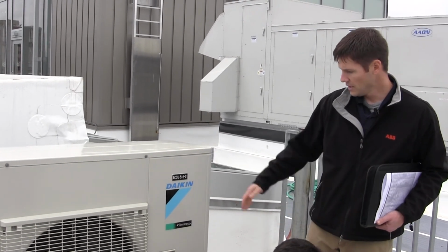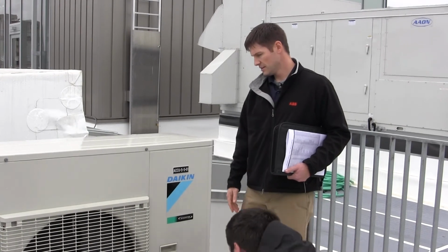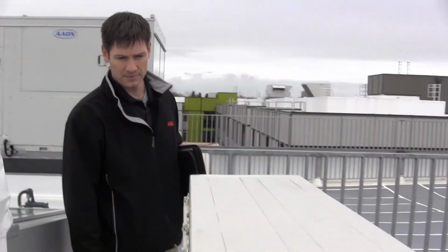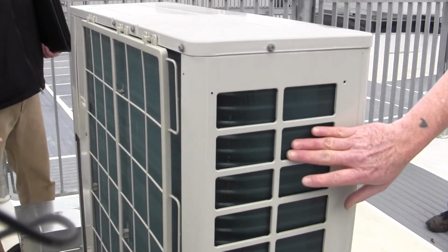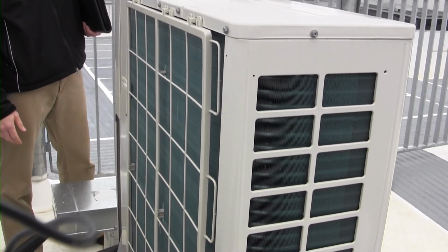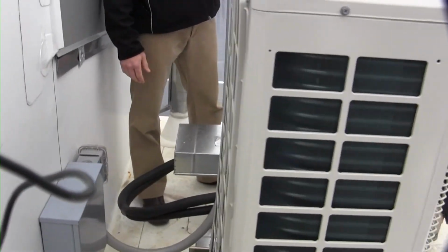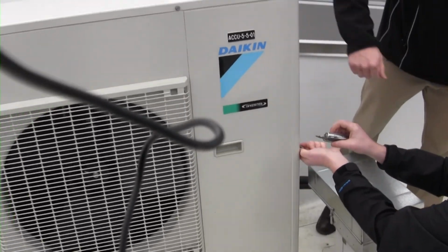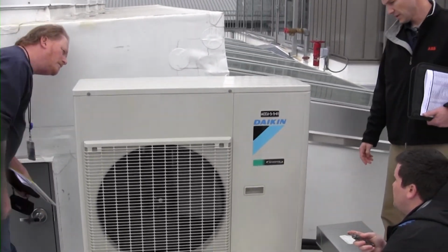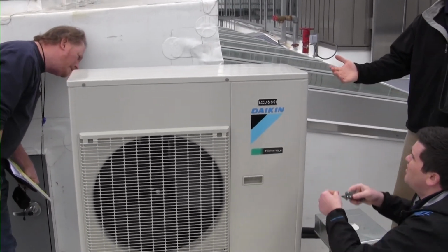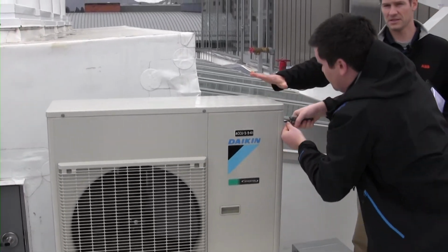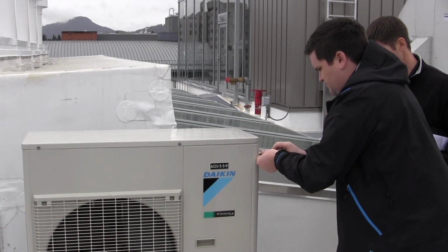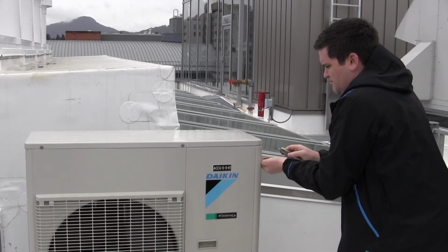On the inlet side over here, you can see the coil is slightly blue. That's an acrylic anti-corrosive coating. Very thin layer, doesn't change any heat transfer properties. The air gets drawn through and comes out the fan on this side. And since this unit will always be cooling indoors, that means this is basically heating, so it's not going to produce condensate. It's always going to just dispense of heat.